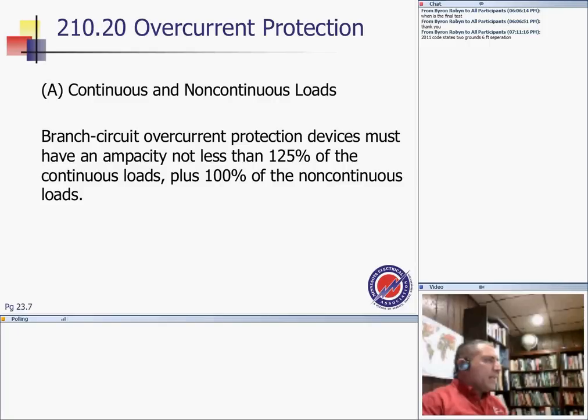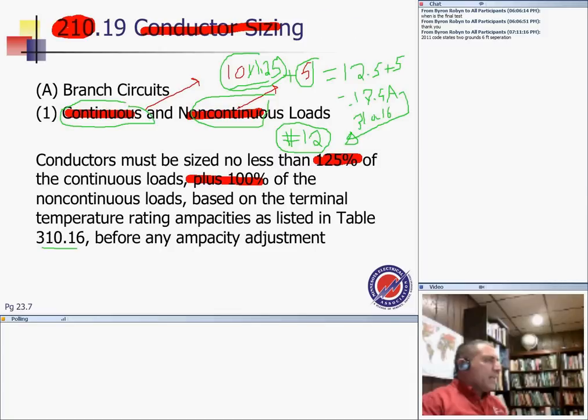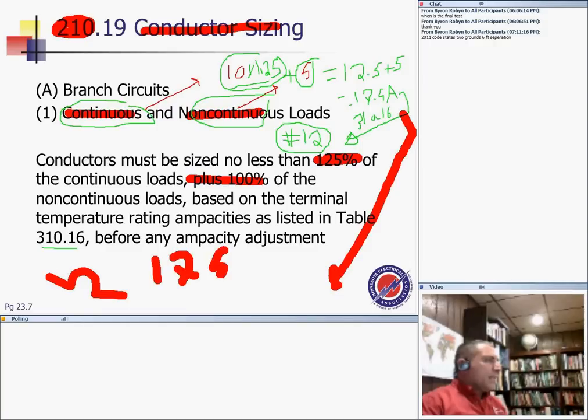Now guys, for the overcurrent device, when you size the overcurrent device, there are things for continuous and non-continuous. So back to my example, if I size the overcurrent device right now, I came up with 17.5, the same calculation. You're going to take this one to 240.6. That's where you have the standard overcurrent devices, non-adjustable. And the next standard after 17.5 is a 20 amp circuit breaker.